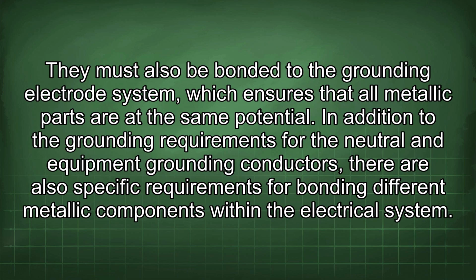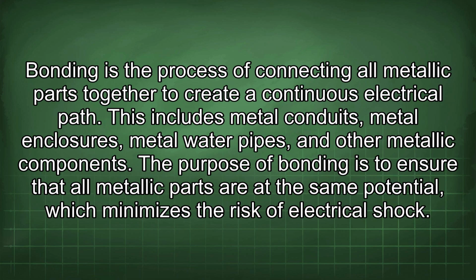They must also be bonded to the grounding electrode system, which ensures that all metallic parts are at the same potential. In addition to the grounding requirements for the neutral and equipment grounding conductors, there are also specific requirements for bonding different metallic components within the electrical system. Bonding is the process of connecting all metallic parts together to create a continuous electrical path.